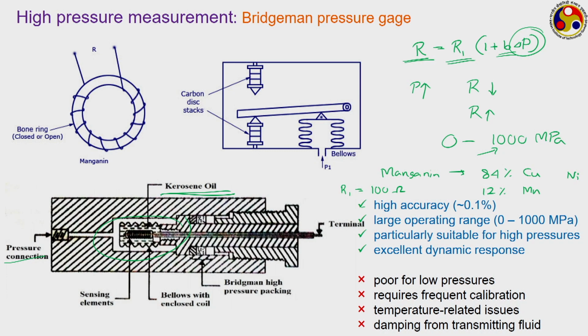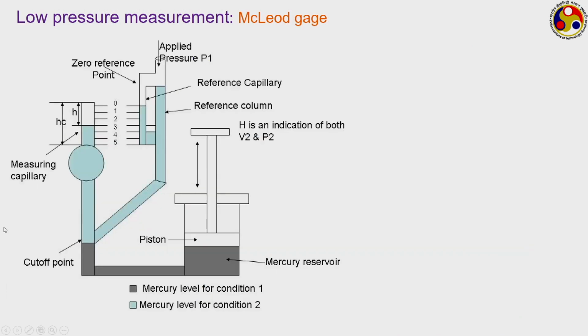Next we go to low pressure measurement. Low pressure measurement, we often call them vacuum pressure as well, because here we are talking about very small values of pressure well below the atmospheric pressure level, which we conventionally call the vacuum pressure. Now, as we have discussed earlier, the common unit that we use for measuring vacuum pressure is torr. 1 torr is just 1 millimeter of mercury column.